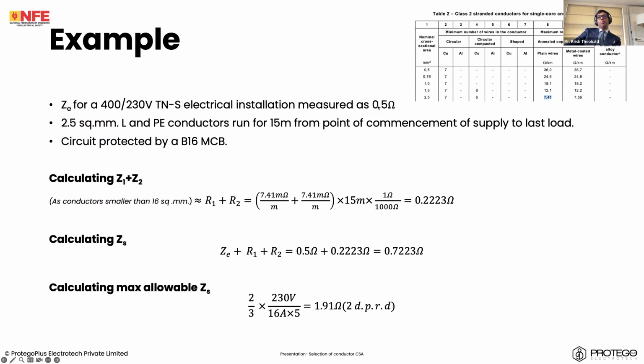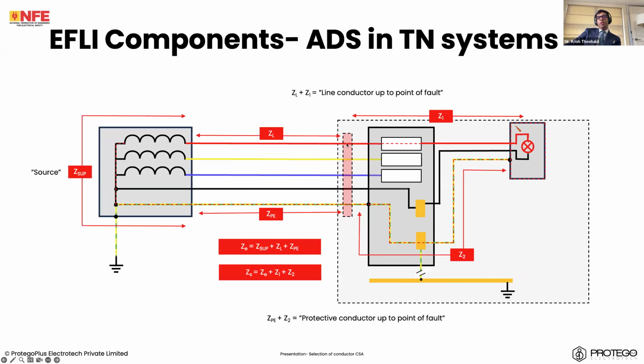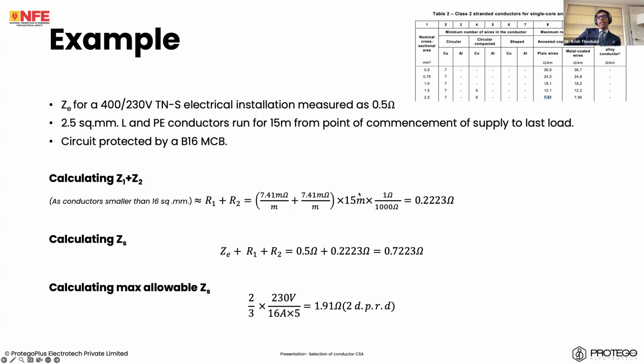Add this to the earth fault loop impedance measured here at the point of commencement of supply. So Z sub e plus ZL plus ZP is 0.5. Z1 plus Z2 is 0.2223. So 0.5 plus 0.2223 is 0.7223. What is the maximum allowable Zs? Well, 230 volt is a single phase circuit. 16 amp is the breaker. So B16, times 5, we get 1.91 ohms. So 0.7223 is lesser than 1.91 ohms. We are happy. Our loop impedance value is satisfied.